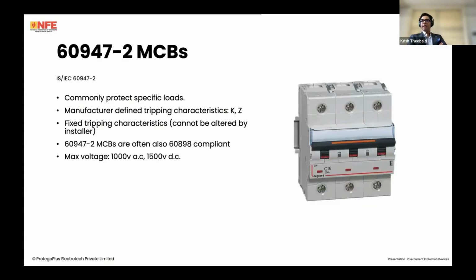Then you've got the slightly more specialized MCB. These are 60947 Part 2 MCBs. These commonly protect specific loads, and here the manufacturer can define a tripping characteristic. So often you see a type K or a type Z MCB. These are actually manufacturer defined. They're not in a standard, they just conform with the standard. Once again, these MCBs have fixed tripping characteristics, so they will trip at a defined multiple. We'll look at exactly what a type K and type Z are. They are more common amongst the other manufacturer-defined tripping characteristics.